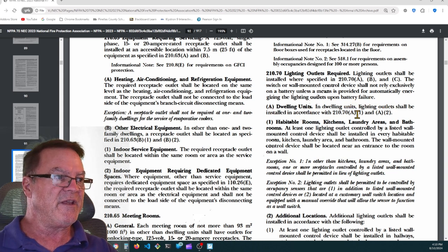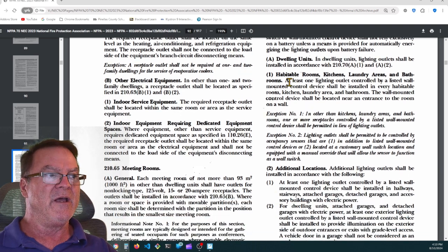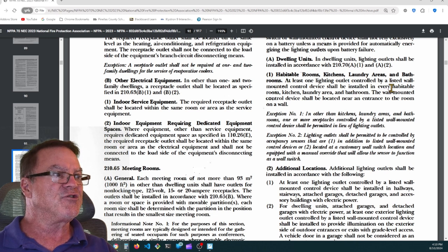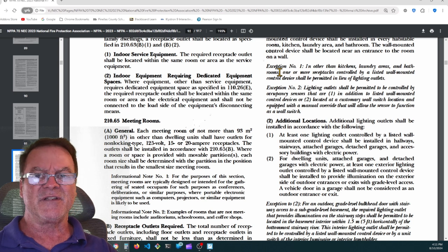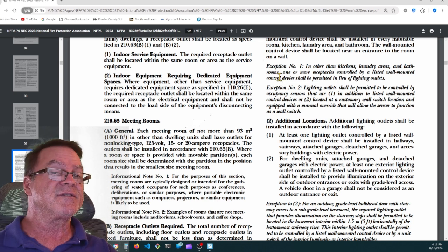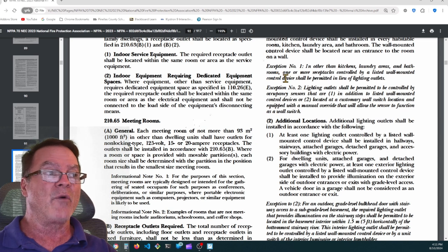A. Dwelling units. In dwelling units, lighting outlets shall be installed in accordance with 210.70(A)(1) and (2). Every habitable room. Habitable rooms, kitchens, laundry areas, and bathrooms. At least one lighting outlet controlled by a listed wall-mounted control device shall be installed in every habitable room, kitchen, laundry room, and bathroom. The wall-mounted control device shall be located near the entrance of the room on a wall. And then they give you an exception. They say you can use an occupancy sensor if it's located in the same location as the switch and has a button to override it.